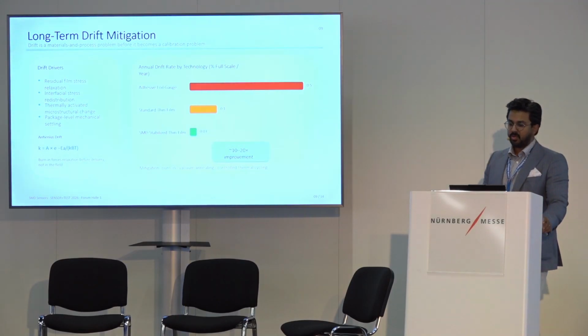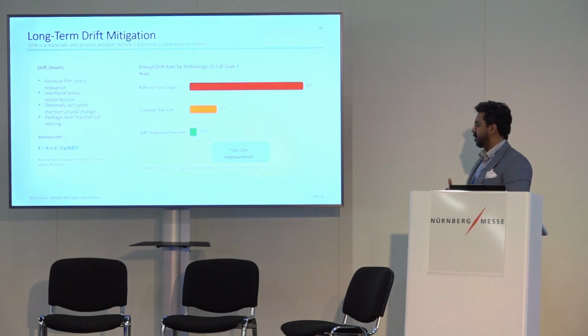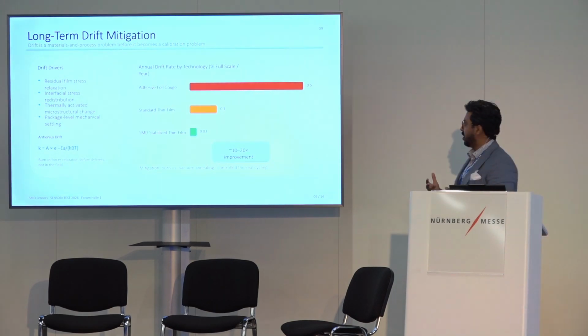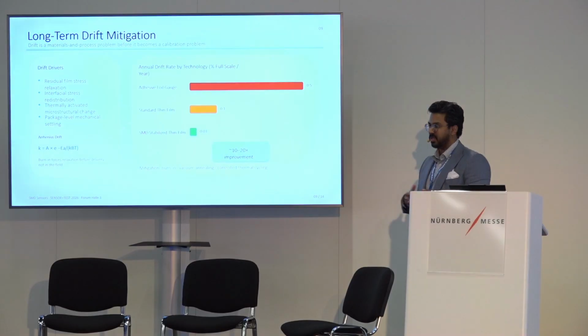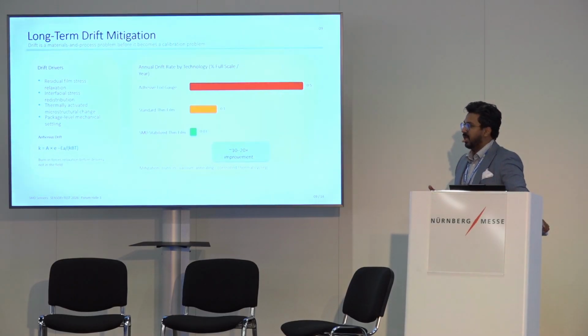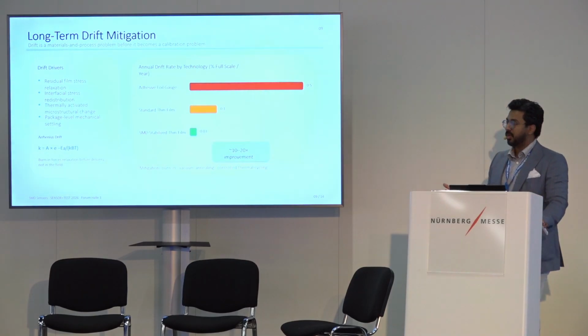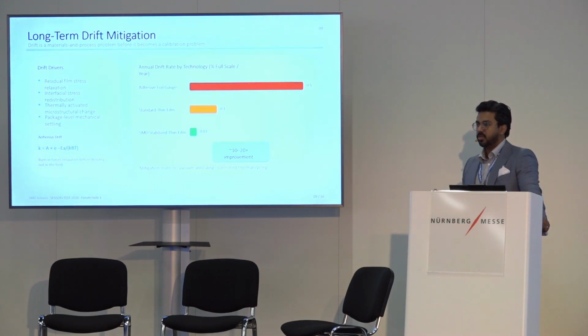So when you do this, of course, it depends on the requirement, but if you have the adhesive foil gauge that we talked about, you would see the drift is like 0.5 percent full scale per year. And that is very normal. That actually defines the prices of these strain gauges. You can find it at less than $1, or you can find our sensors, which could be much more expensive, but you would see 10 to 20 times improvement compared to even other standard thin film processes. So that's where the price difference comes in when designing these high pressure, high temperature applications, pressure sensors, which are validated from strain gauges.